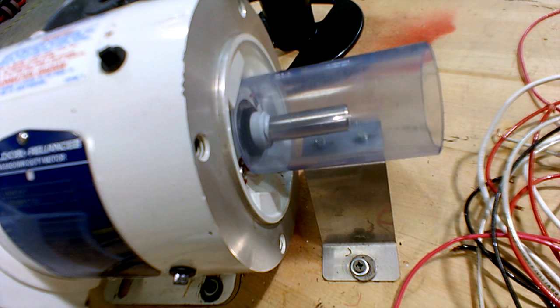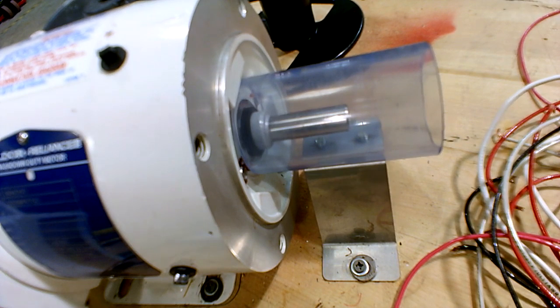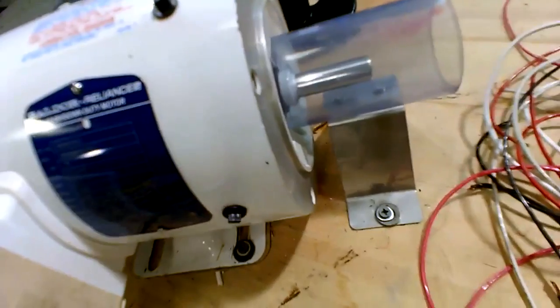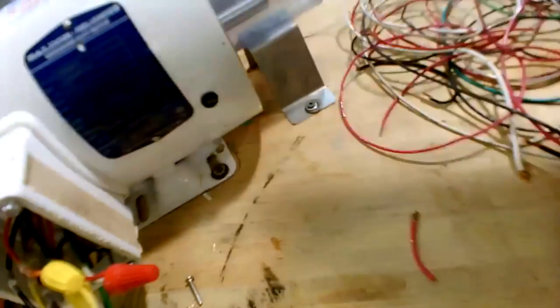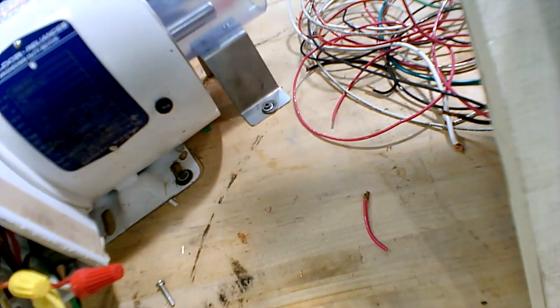So now you can bump the motor on and now cut it off. And as you see, it's going counterclockwise. So that's how you do it manually. If it's just a regular starter, you just flip any two of the legs that go to the motor. And that, you leave that on. We're going to run, let you just test.